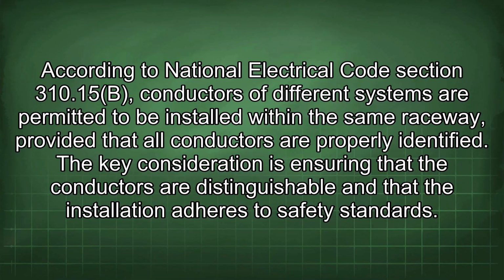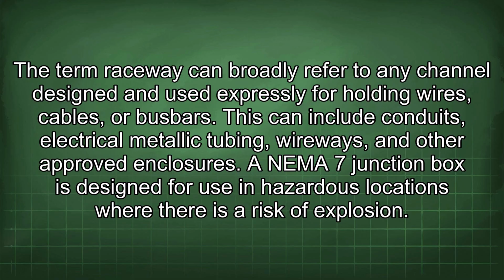According to National Electrical Code Section 310.15(B), conductors of different systems are permitted to be installed within the same raceway, provided that all conductors are properly identified. The key consideration is ensuring that the conductors are distinguishable and that the installation adheres to safety standards. The term raceway can broadly refer to any channel designed and used expressly for holding wires, cables, or busbars. This can include conduits, electrical metallic tubing, wireways, and other approved enclosures.